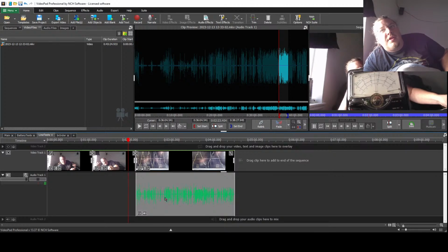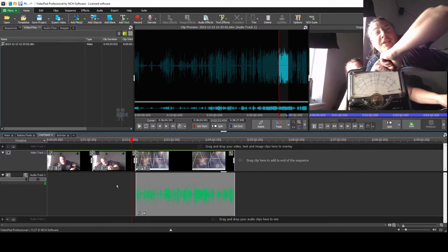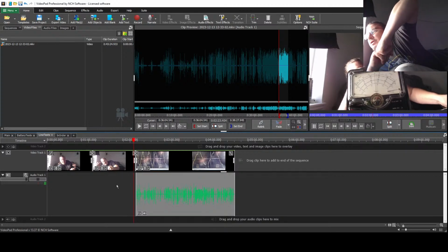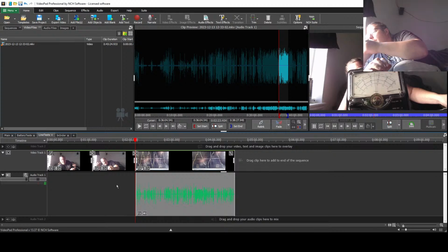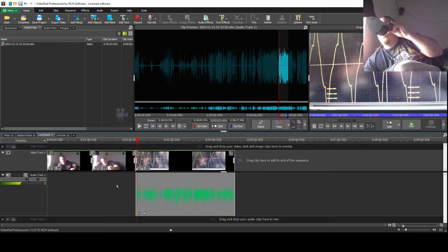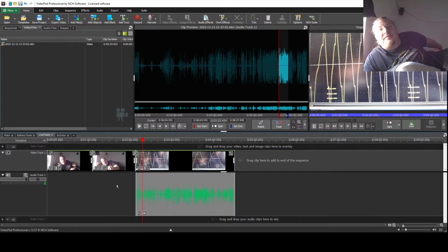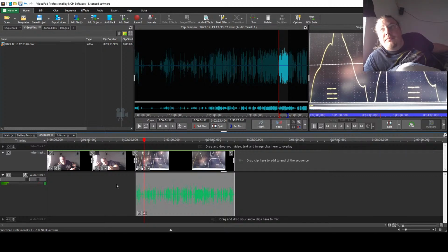I don't know if there's anything useful in here audio-wise. So we're gonna let it play. Now that is the waveform coming out of the wall for Logan, Utah. Now we can see what is supposed to be a sine wave has a lot of artifacts. Okay, you've got this jiggly bit here.